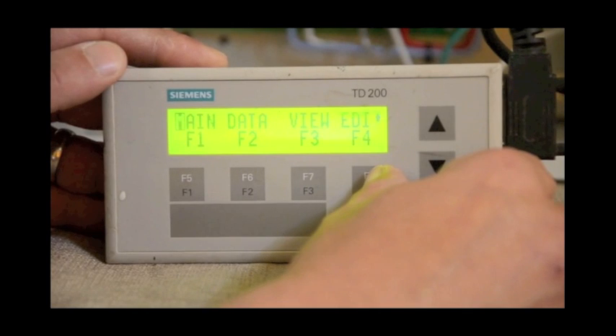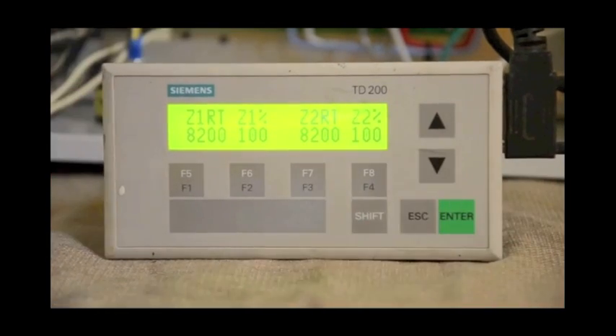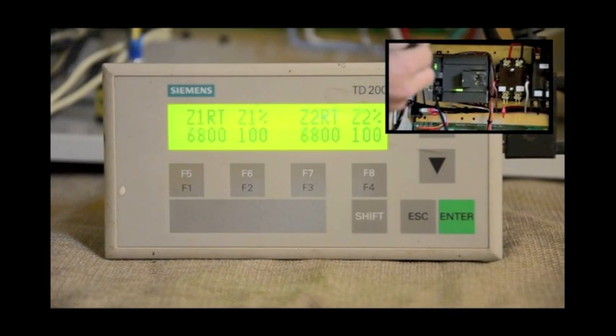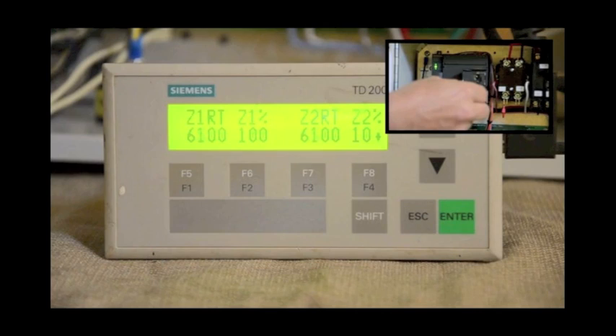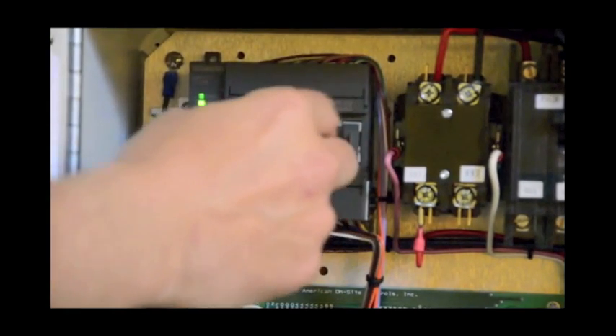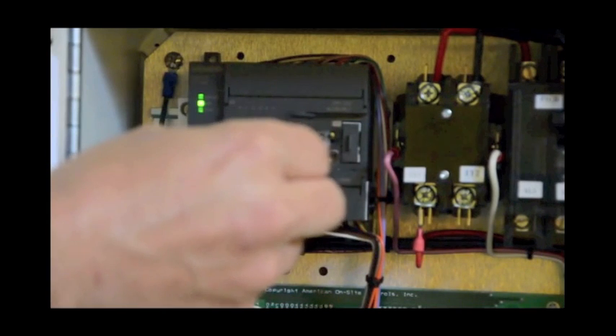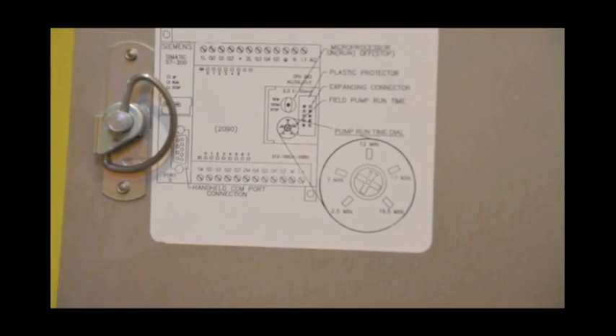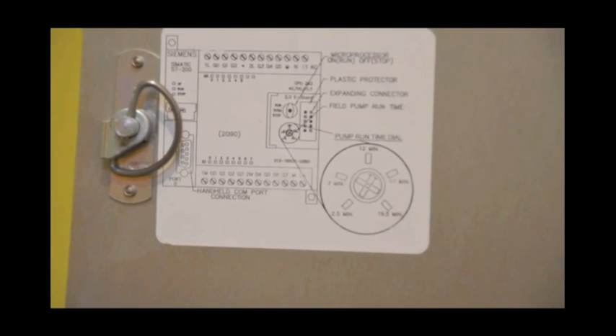The pump run time is displayed under the edit screen, displayed independently for each zone and adjusted using a small screwdriver on the PLC. You can adjust the pump run set screw either up or down. You'll notice the numbers are changing on the edit screen. They change the same for both zones. Pump run times can be adjusted without using a handheld. They can be done with a little trial and error with a small screwdriver on the PLC. Using this method, pump run times are limited to 2.5 to 19.5 minutes.